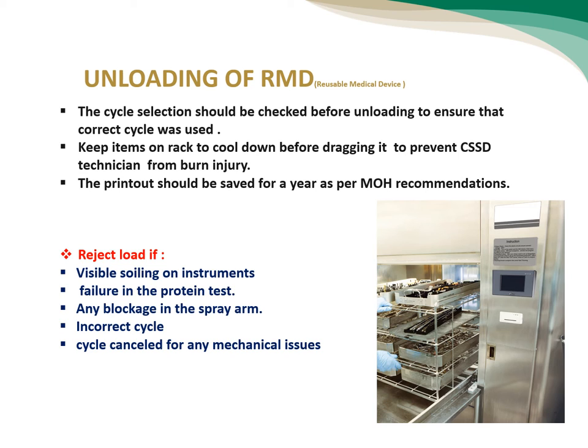Cycle cancel for any mechanical issue, maybe there is a failure of water, a failure of electricity, or something wrong with the system of the washer disinfector. For these five things, we have to reject all the load and reprocess it again from the beginning. It means to restart the washer disinfector for it. That's okay.